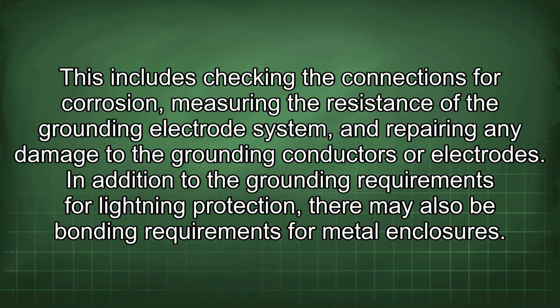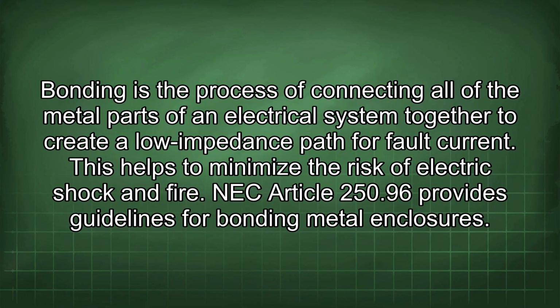In addition to the grounding requirements for lightning protection, there may also be bonding requirements for metal enclosures. Bonding is the process of connecting all of the metal parts of an electrical system together to create a low impedance path for fault current. This helps to minimize the risk of electric shock and fire.